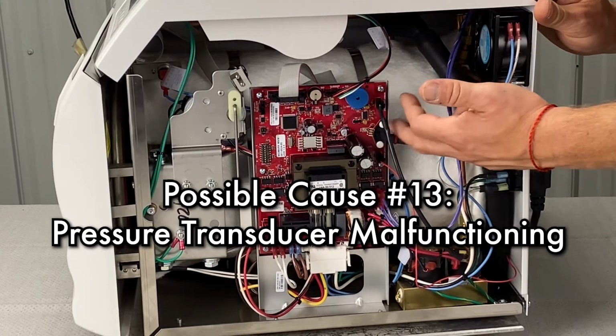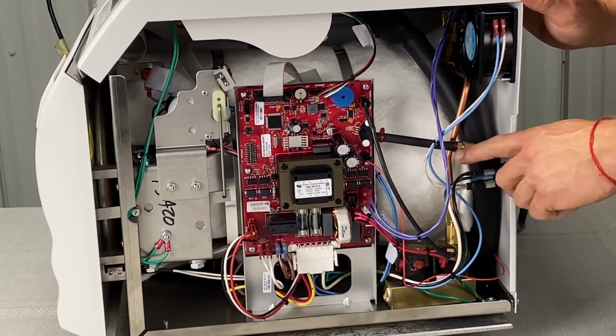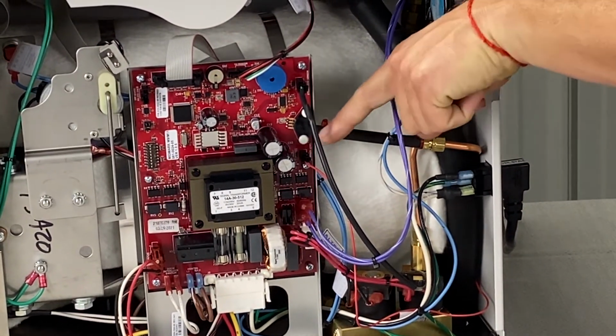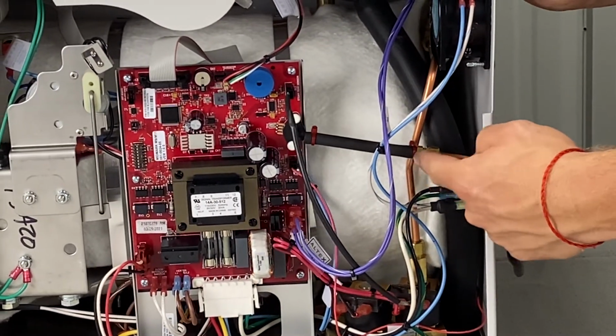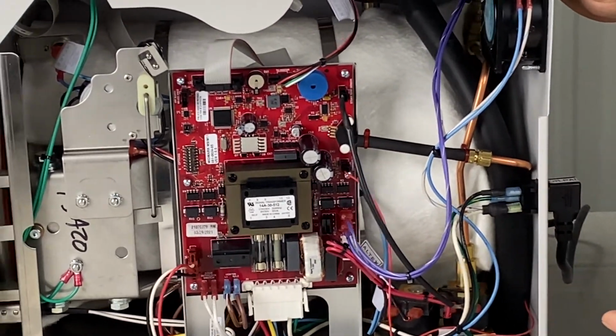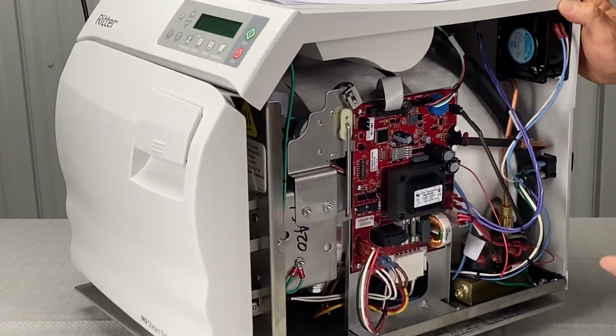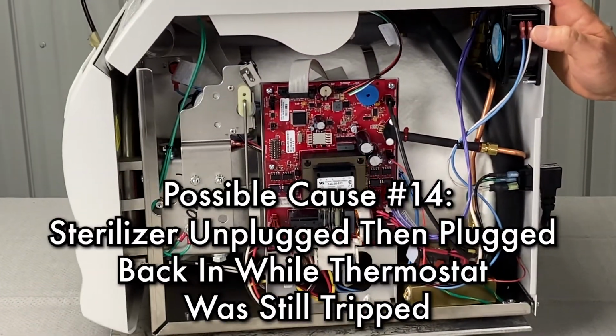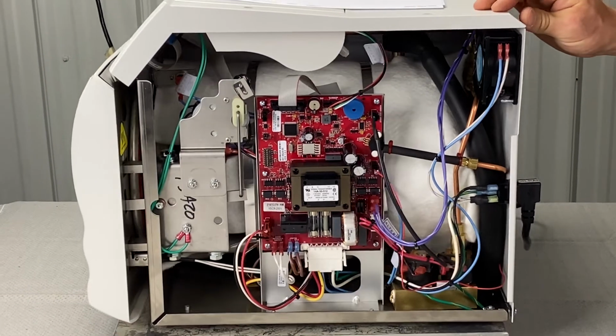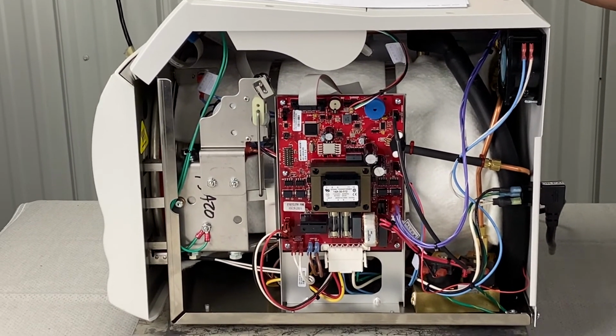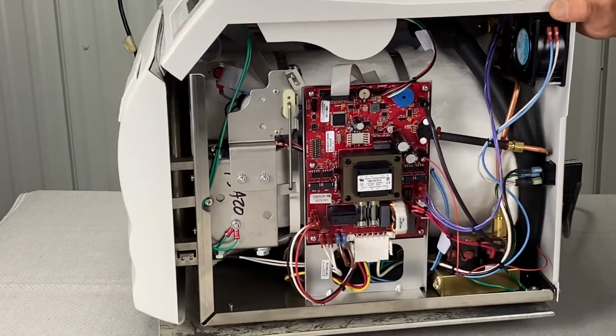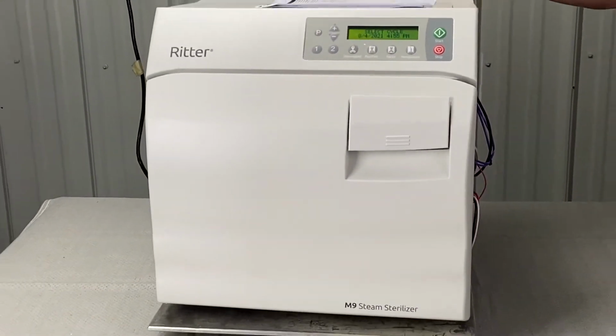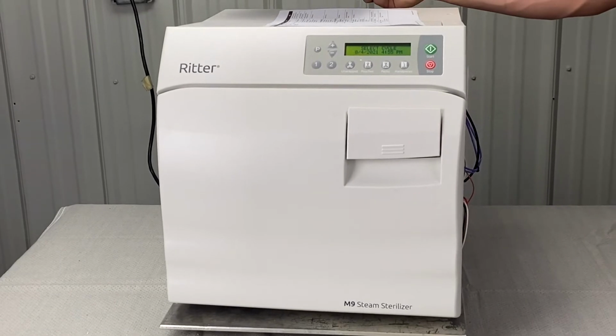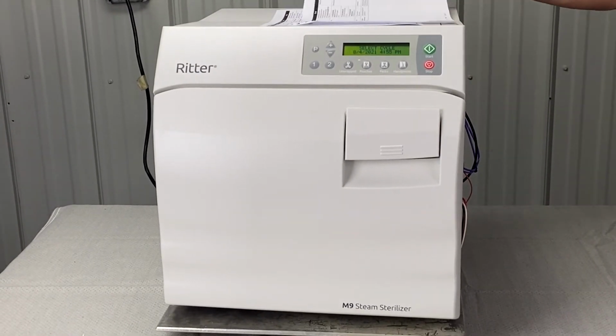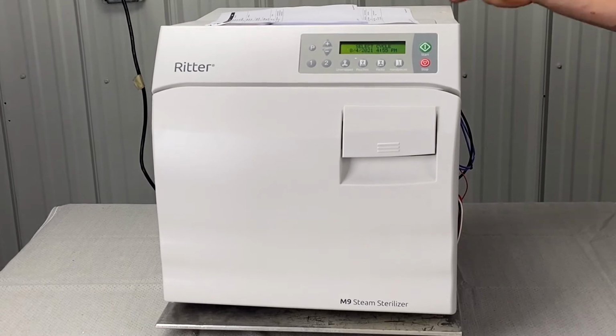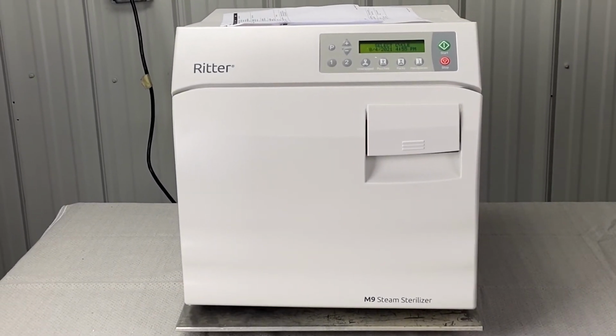Could be pressure transducers. It's giving faulty readings. Possibly the pressure tubing is pointing down. It should be always pointing in this position. And also very basic, if the sterilizer was unplugged and then plugged back in while the thermostat was still tripped. So, back at the reset point, that could also happen. So this is Charlie 987. Could be a lot of different things. Door springs, high limit thermostats, temp sensors, line voltage, multiple units on one outlet.